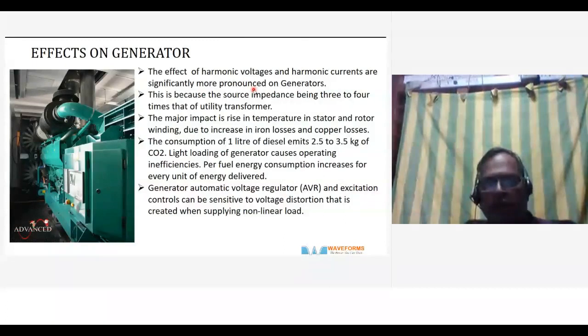The major impact is rise in temperature in the stator and rotor winding due to increase in iron losses and copper losses. Consumption of 1 liter of diesel emits 2.5 to 3.5 kg of CO2, so it is environmentally unfriendly also. Light loading of a generator causes operating inefficiency, so your operation cost of the generator also goes up. So fuel energy consumption increases for every unit of energy delivered. So the unit consumption of energy also goes up substantially if you have harmonics.